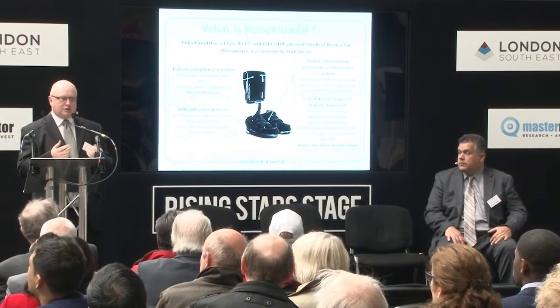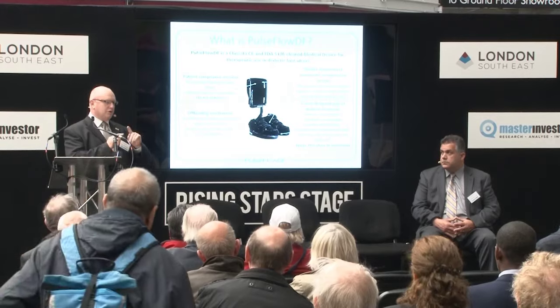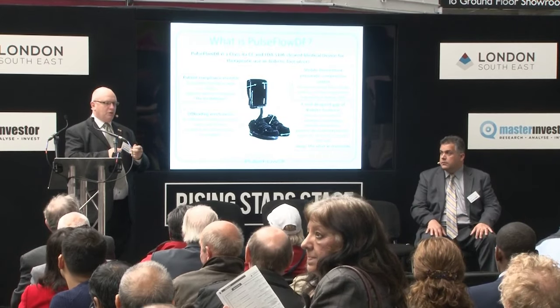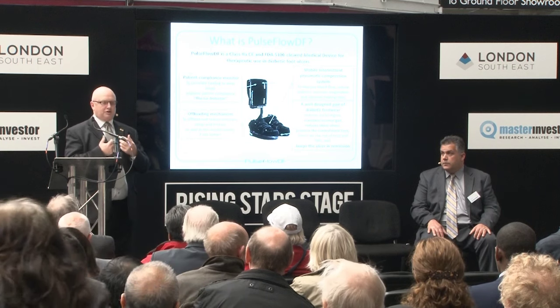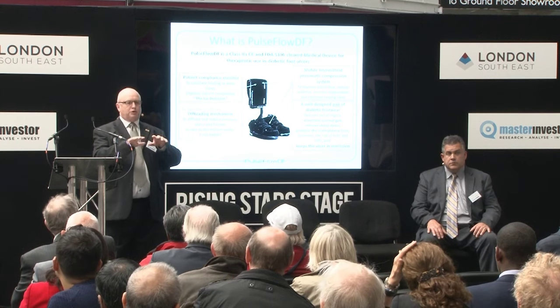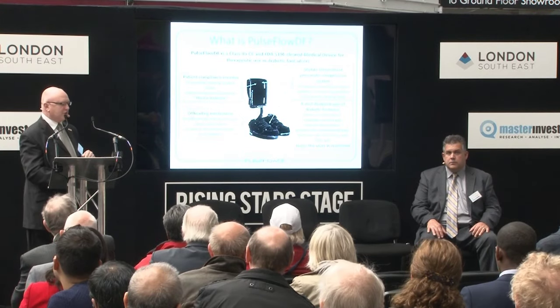And one of the things the doctors have said to us is, "We don't mind you giving us a therapy if it heals the wound. That's fantastic. Is there any way you can stop the wound breaking down again?" Because what we're sick of is we do a great job, we get the patient to heal, he goes home, he wears his old footwear again, and it breaks down in exactly the same place. Well, the answer is yes. We've made it so that the mobile compression device comes out and the patient goes home with the footwear to protect it for a couple of months and let the wound toughen up again so it doesn't break down. So that's a very, very quick run through of what this class 2 product is.